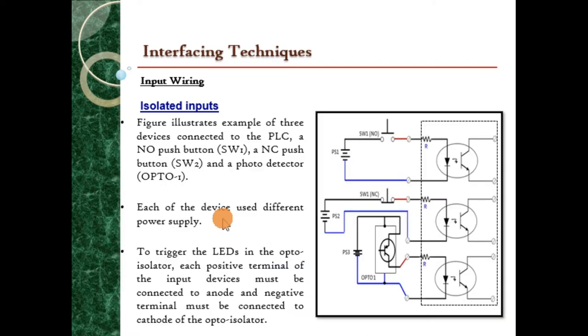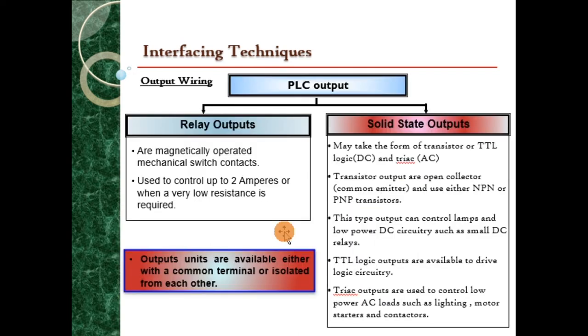So meaning that each input has its own positive and negative terminal. This is the example of three devices connected to the PLC, where each of these devices is an isolated device. You can see here it has its own positive and negative terminal for each device, and there is no common contact between these devices. So as we have been introduced to the input wiring of the PLC using the opto-isolator, now we move to the output wiring of the PLC.